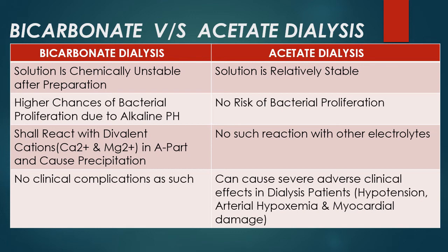Another problem with bicarbonate dialysate solution is that the carbonate present in the bicarbonate solution will react with the divalent cations present in acid concentrates — such as calcium ions and magnesium ions — thereby forming a chemical precipitation, meaning crystal formations. For acetate dialysis, there is only one concentrate which is diluted with water, so there is no precipitation.